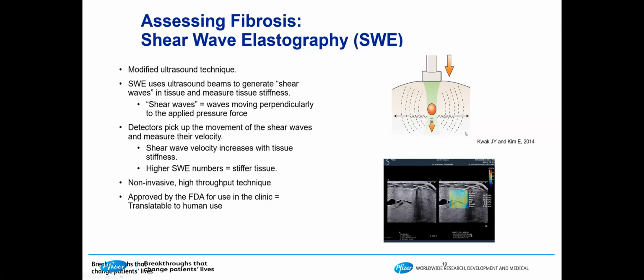The basic principle behind this shear wave elastography is, you have a transducer which sends a very high frequency ultrasound through the soft tissue, and this high frequency ultrasound, when it travels through the soft tissue, reverberates the soft tissue perpendicular to the axis of the high frequency ultrasound, which creates shear waves within the soft tissue. So the transducer has the ability to measure the speed at which these shear waves travel perpendicular to the high frequency ultrasound upon applying it over the tissue.